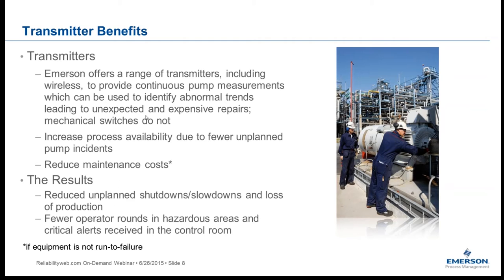The primary benefit of providing these measurements is to increase process availability — to keep running and reduce unplanned incidents. If it's detected that a pump needs maintenance, it can be taken out of service in a calm, controlled manner rather than after the seal has already failed. Operations can plan for parts and maintenance, and damage may not be as severe as if run to failure. Additionally, sensors in the field reduce the burden on operators who would otherwise need to take frequent manual rounds to collect data.